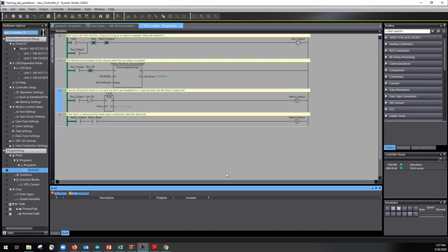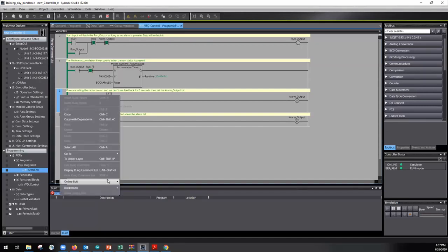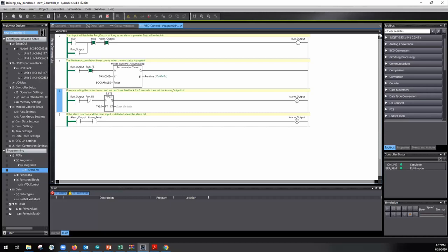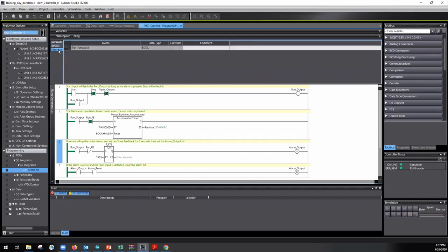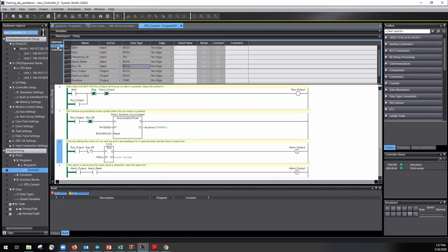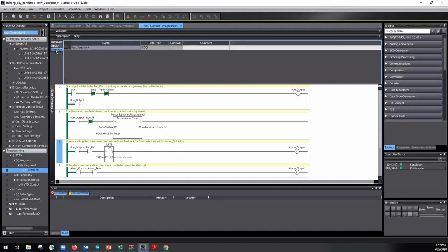So it's actually one thing that sets us apart from a lot of platforms: we can edit our custom function blocks online. Now that being said, I will make you aware of some restrictions with that. We can change logic and we can work with variables that we've already created in our online edit. But as far as creating in-out variables up here, it is something that we can't do. We can add a new external variable and we can create a new global variable in our PLC to go with it. But we can't modify our in-out variables, only our internals and our externals.